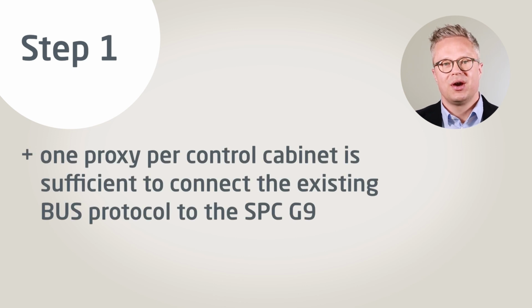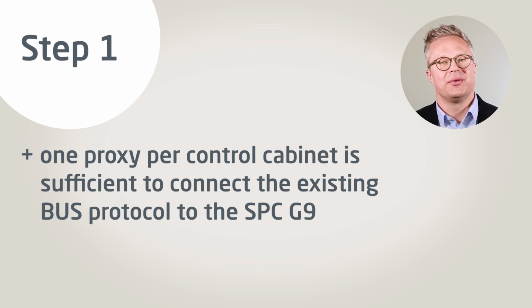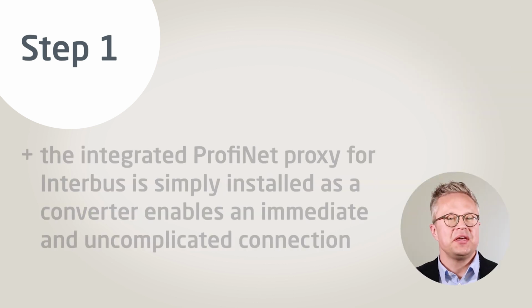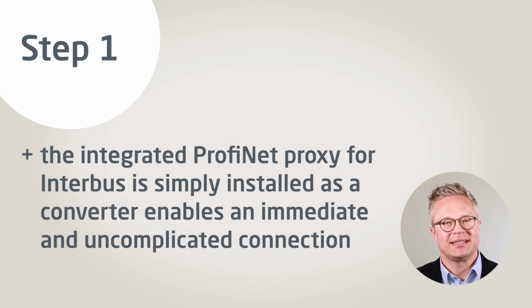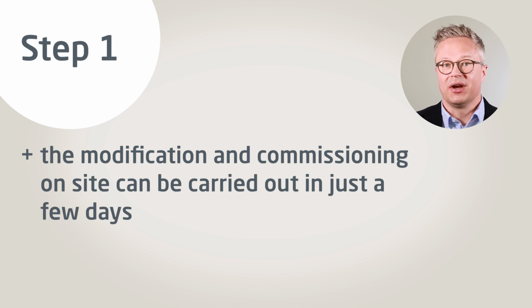As previously mentioned, in principle, modernizations are feasible for both market leaders of control systems, namely Siemens S7 and Rockwell ControlLogix. They can be carried out in 2 steps. Step 1. If the Interbus is to be preserved, one proxy per control cabinet is sufficient to connect the existing bus protocol via a fieldbus based on the real-time Ethernet to the SPC G9. The integrated Profinet proxy for Interbus is simply installed as a converter in the respective control cabinets and enables an immediate and uncomplicated connection of the Interbus components to the new SPC G9 system. Due to the system-side adjustment of the software X-Work, the modification and commissioning on site can be carried out in just a few days. This avoids long downtimes.